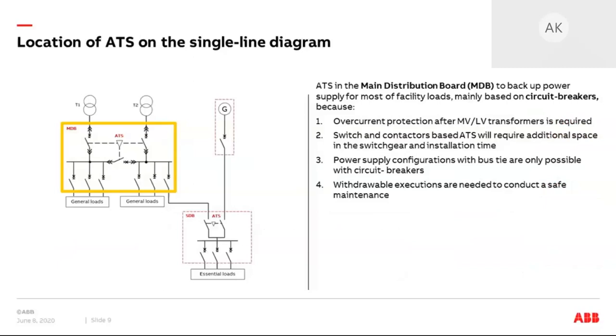ATS based on circuit breakers is usually used in main distribution boards to provide continuity of power for most facility loads. Circuit breaker-based ATS is the preferable choice because overcurrent protection is required after the medium voltage/low voltage transformer, and this is integrated in the ATS. Using a switch or contactor-based solution would require additional space and installation time. Some power supply configurations with a tiebreaker — for example made with IMA — are only possible with circuit breaker-based ATS. Additionally, circuit breaker-based ATS can be in withdrawable execution to provide visual isolation for maintenance.